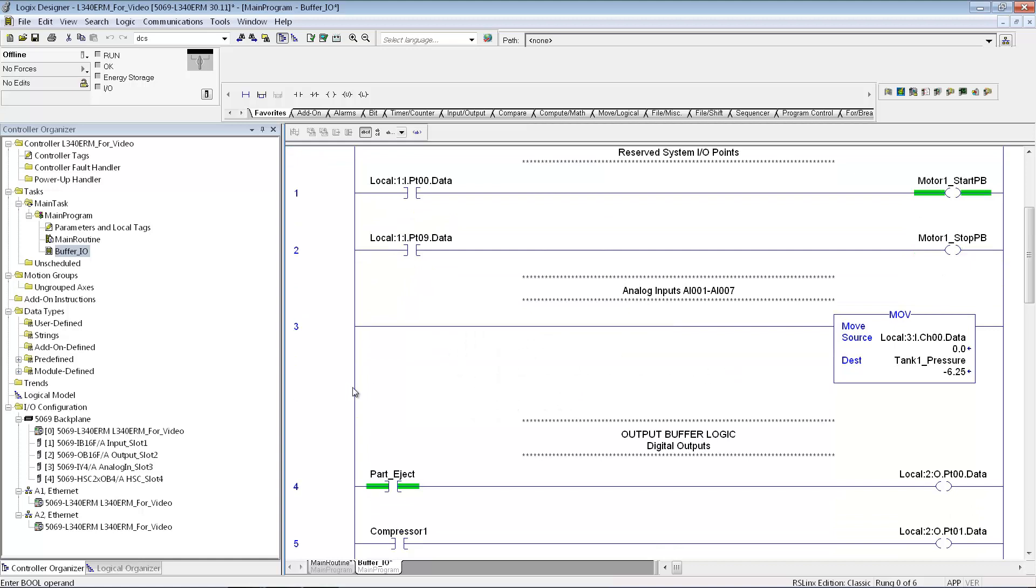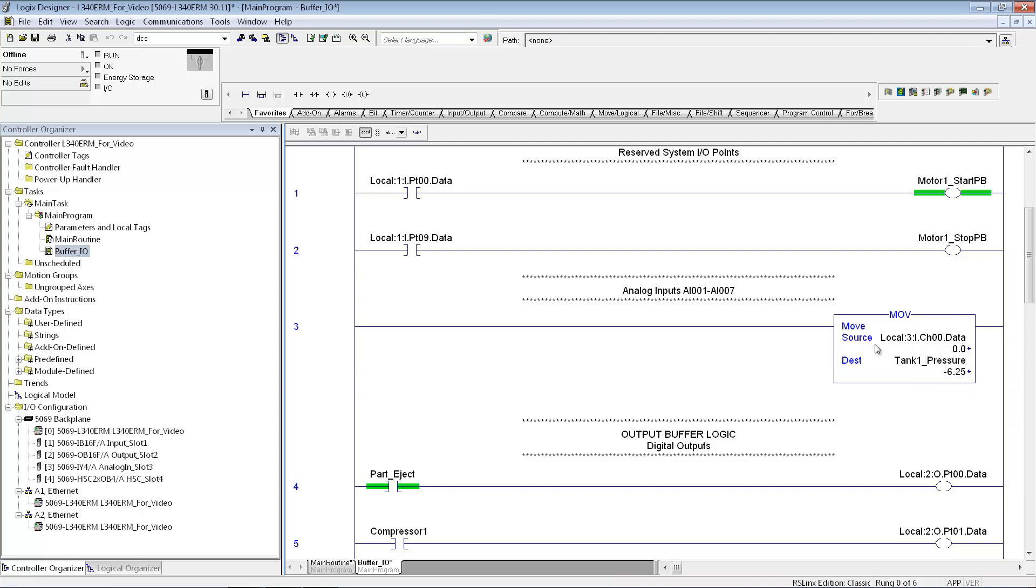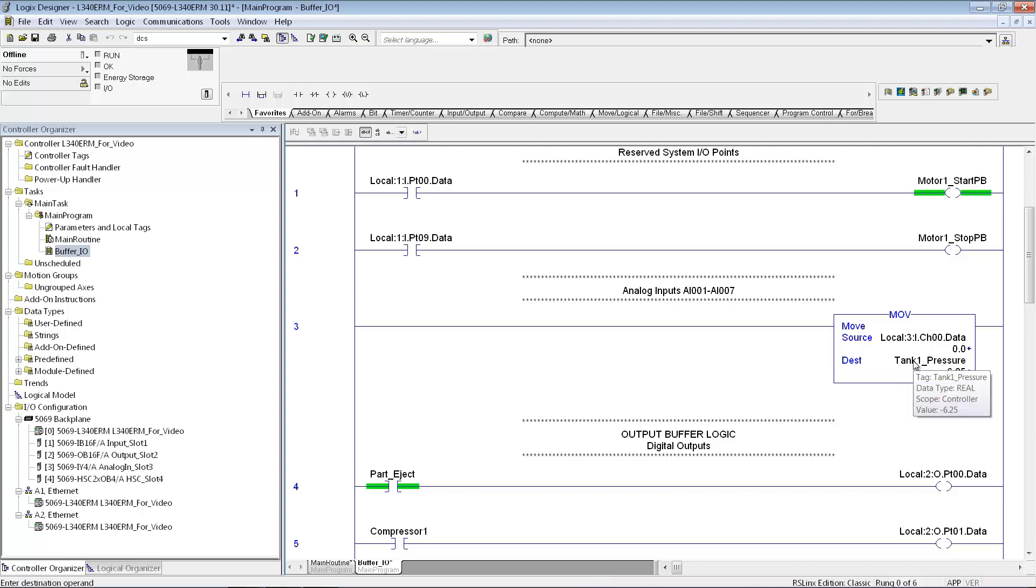If I have an analog input, for instance, my IY4 is an analog module, I'm going to just do a move and take that input word, the first input point in that module, and I'm going to have that go to something I call tank one pressure, and I make that a real tag in my controller tags.